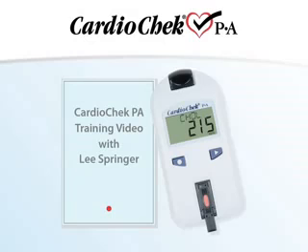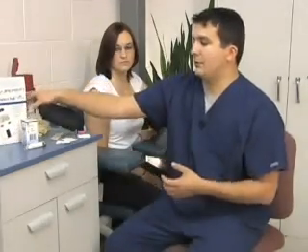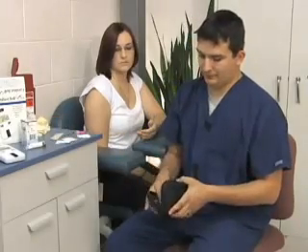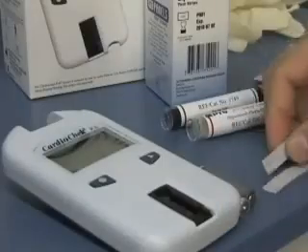Thank you for choosing the CardioChek PA test system for your point of care testing needs. In order to perform a test you need several things: the instrument and then the test strips. Inside the box with the instrument there are several items: the CardioChek PA instrument itself, two AAA batteries, two gray check strips, and then the black carrying pouch.